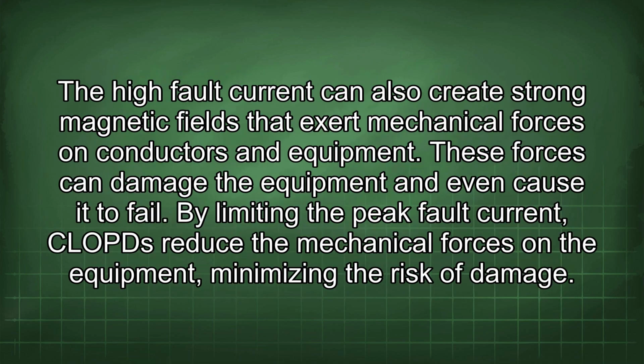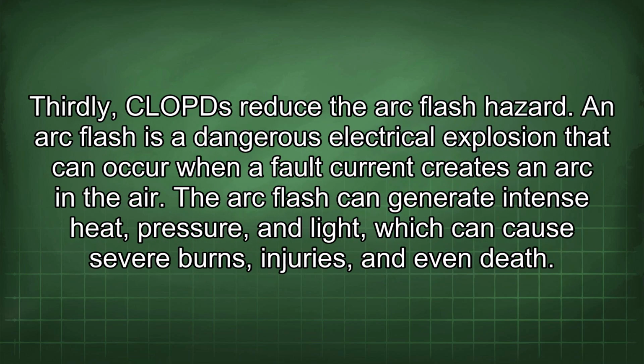The high fault current can also create strong magnetic fields that exert mechanical forces on conductors and equipment. These forces can damage the equipment and even cause it to fail. By limiting the peak fault current, CLOPDs reduce the mechanical forces on the equipment, minimizing the risk of damage. Thirdly, CLOPDs reduce the arc flash hazard.